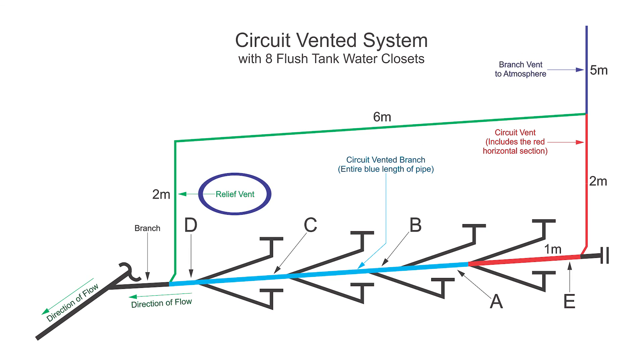Now we need to size the relief vent. Unfortunately, going through the clauses in 2-5-3-1 under the circuit venting section, it doesn't tell us how. The closest thing we get is clause 10, which says additional circuit vents shall be sized in accordance with table 2-5-7-1 and sentence 2-5-7-3-1. Clause 2-5-7-3 is entitled 'additional circuit vents and relief vents' — so we'd better use that.